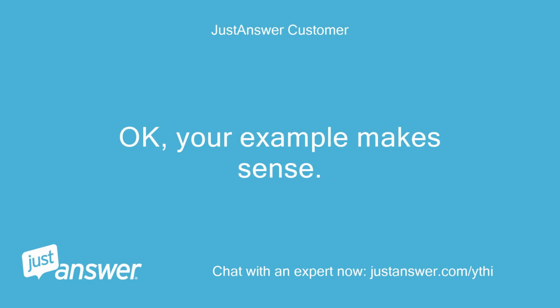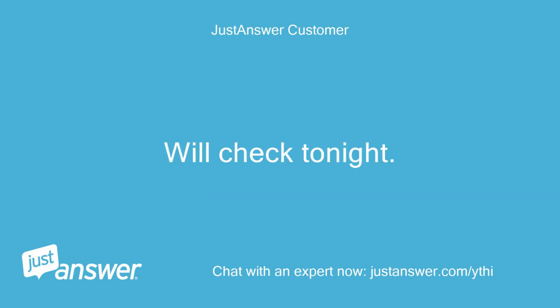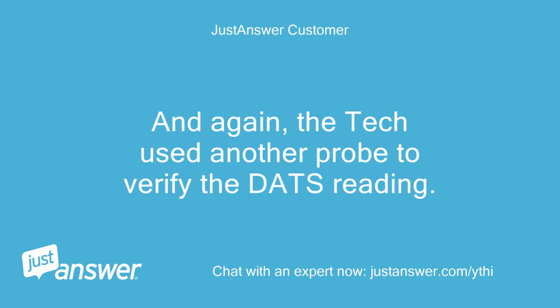Okay, your example makes sense. I have several of the thermometers you mentioned. We'll check tonight. In my experience, though, TCs don't just change their calibration. The value of resistance I measured was almost right on the table value. And again, the tech used another probe to verify the DATS reading.